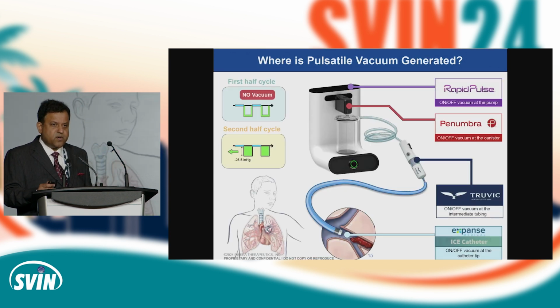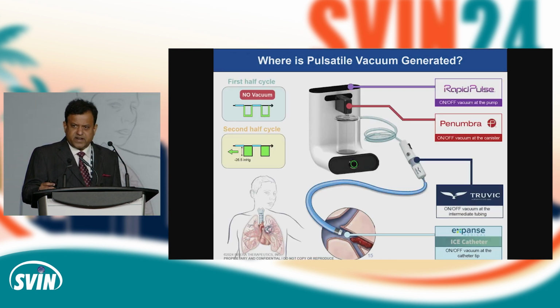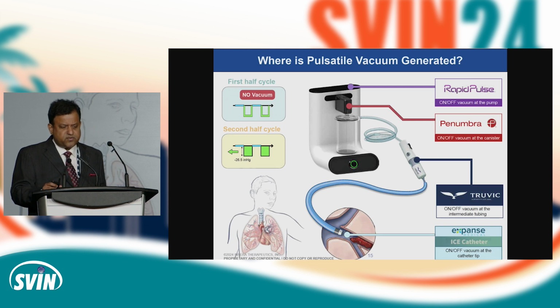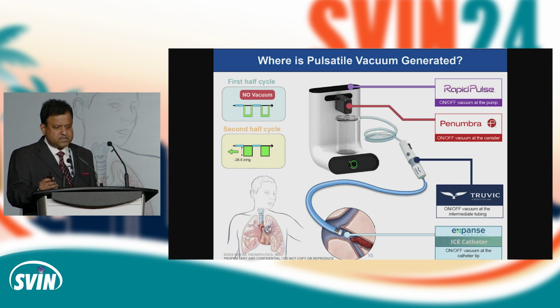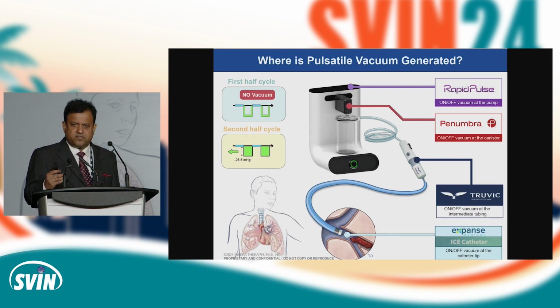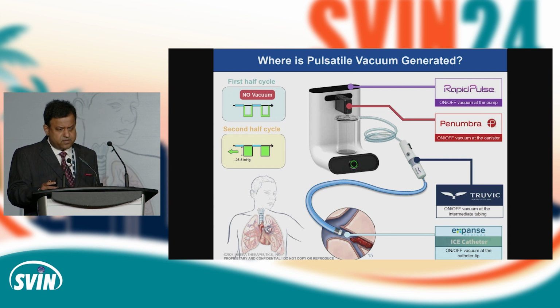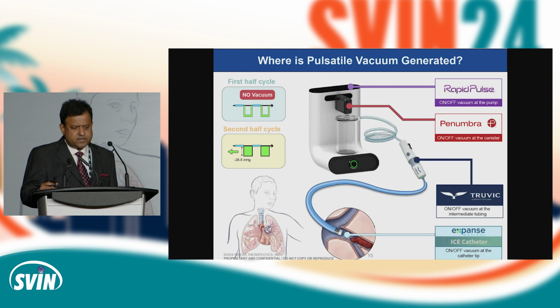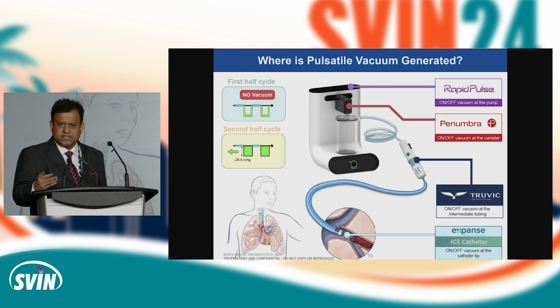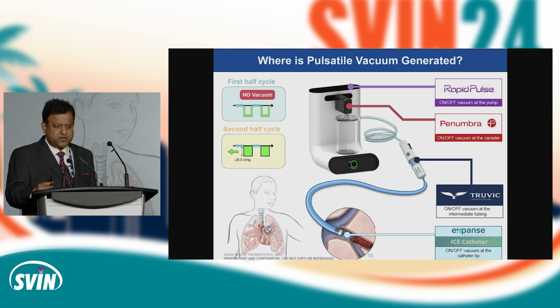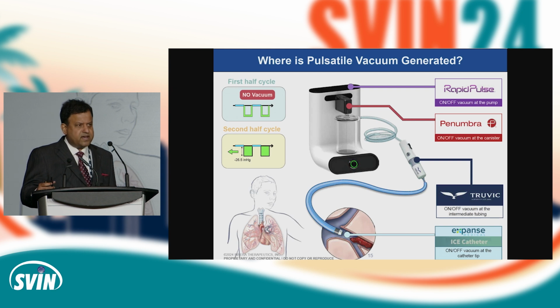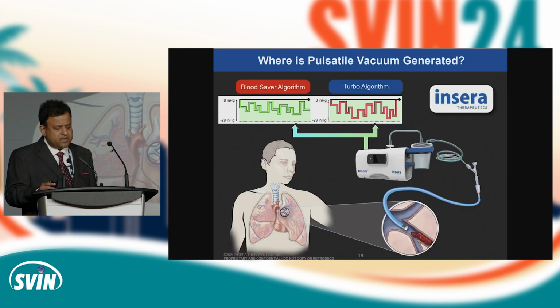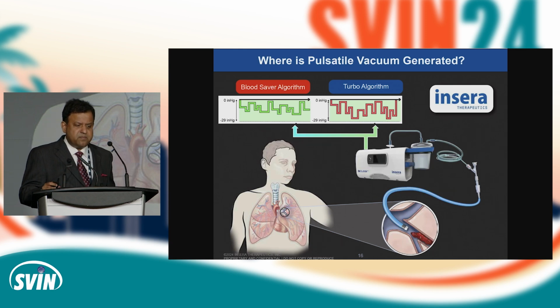Now, if you look at the whole field of augmented aspiration and try to understand the nuances, in the rapid pulse system, the pulsatile vacuum is generated in the generator or the pump. With the Penumbra system, it's an adapter on the canister. With the Truvic system, it's in the on-off switch of the tubing. And with Expanse Ice, it's at the tip of the catheter. With the Insera system, there's a motherboard on the inside of the digital pump, and it generates these algorithms.